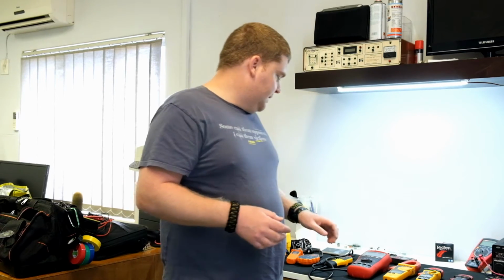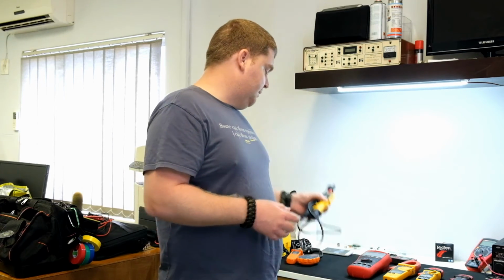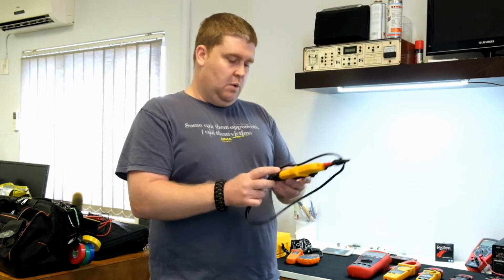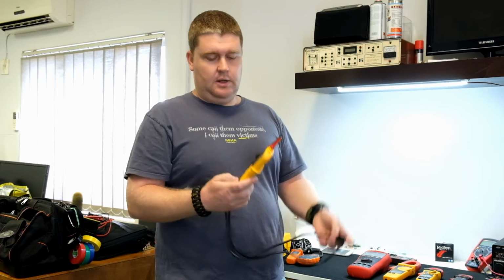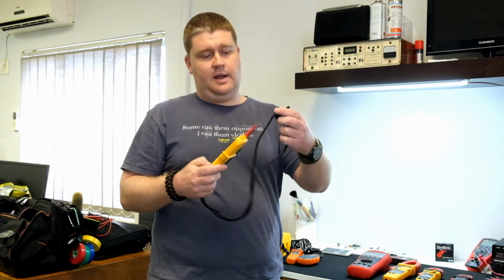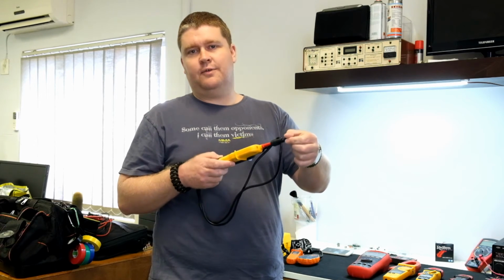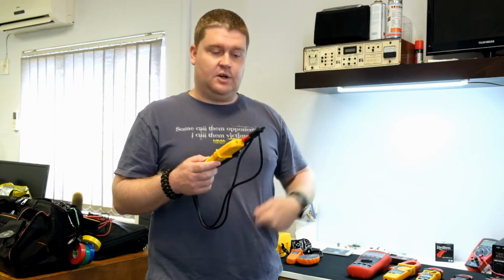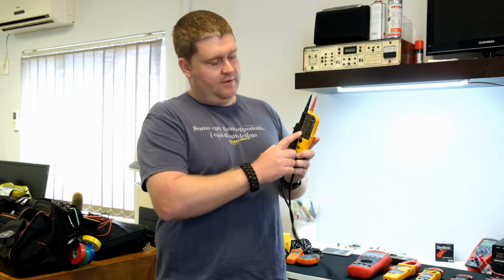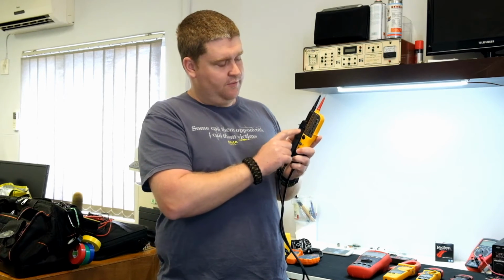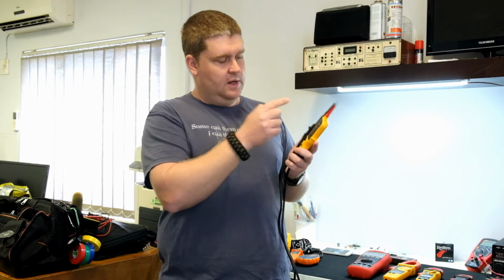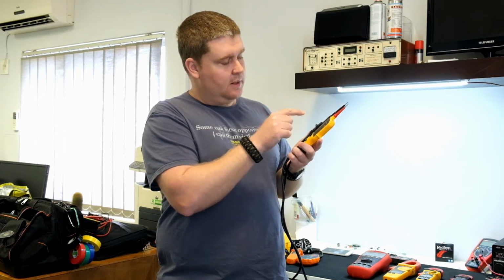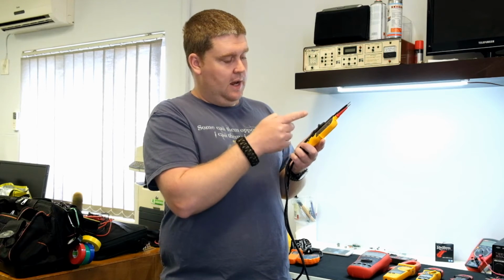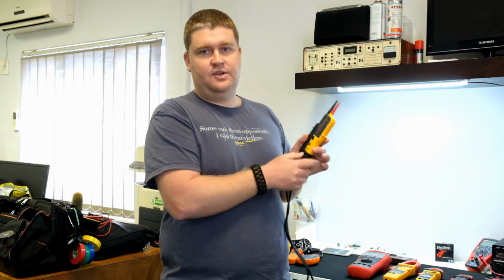Then I'm going to come back to this guy here now, but firstly I just want to point out this Fluke T110. What this basically is a voltage tester. So what happens is, this is just a handy little storage mechanism that they have so you don't damage the probes in the bag, and this is actually designed for opening some AC sockets, but it doesn't work here in South Africa. What this is actually used for is you actually have an LED indication of the voltage from 12 volts to 690 volts. It'll tell you if it's AC or DC. It'll also tell you if there's continuity, and of course it'll tell you your phase rotation.